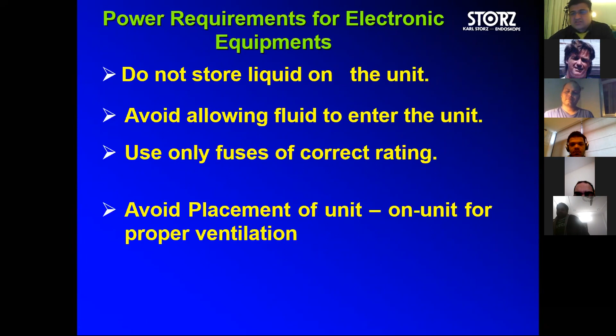And it is important to use the correct rating of the fuses. In our country, in India, and some developing countries, I think everybody is an engineer working in the operation theater among paramedical staff. Anytime a fuse goes, they say, I have a fuse, they take it out from somewhere and put it in. Please note that if the unit says it is a 15 ampere fuse, a 15 ampere fuse has to be used, not a 5 ampere fuse. So it's a little technical, but you should know that the proper repair job should be done by proper people, who are qualified to understand what the rating of the fuse should be.